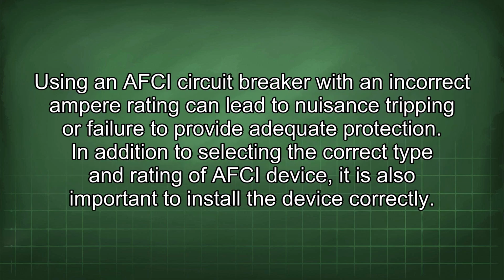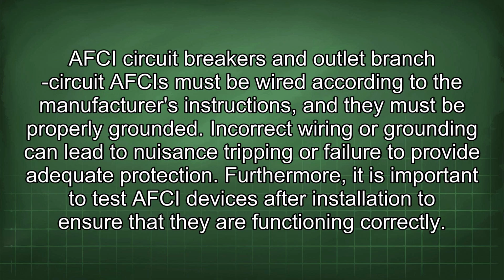Using an AFCI circuit breaker with an incorrect ampere rating can lead to nuisance tripping or failure to provide adequate protection. In addition to selecting the correct type and rating of AFCI device, it is also important to install the device correctly. AFCI circuit breakers and outlet branch circuit AFCIs must be wired according to the manufacturer's instructions, and they must be properly grounded. Incorrect wiring or grounding can lead to nuisance tripping or failure to provide adequate protection.